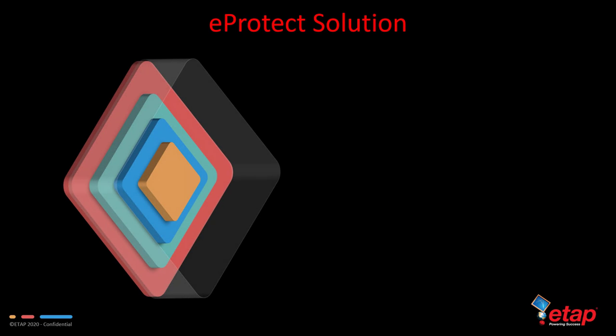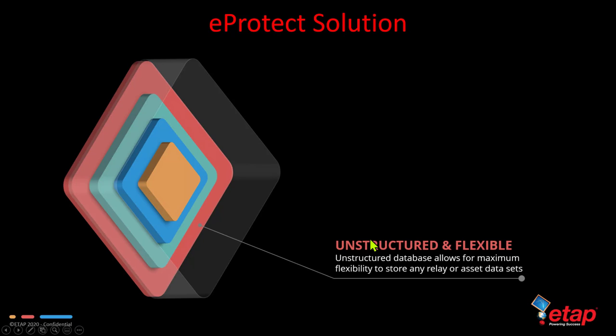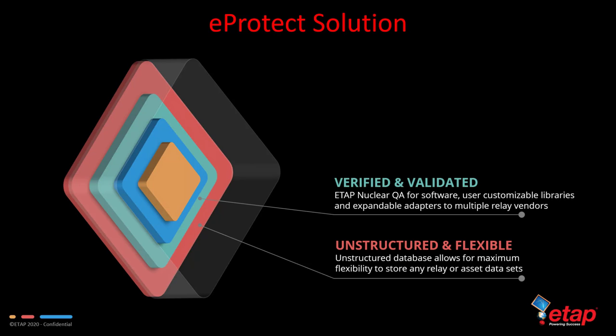And finally, what makes eProtect solution stand out in the industry today is its ability to use an unstructured and flexible database. So this unstructured database allows for maximum flexibility when you're storing any relay or asset data set, because as we know, we can go from one asset to another and increase the number of parameters or properties of that asset by 2 to 3 times. And this essentially requires a database structure that is not so rigid and can accommodate any new device types or even new devices from different vendors.